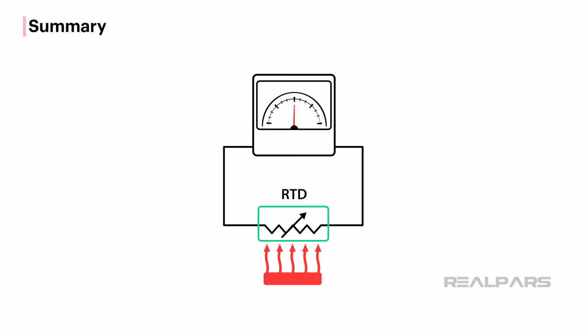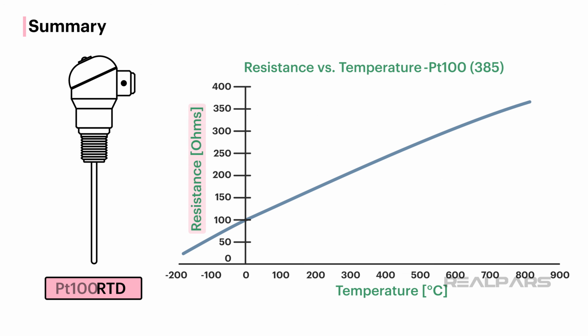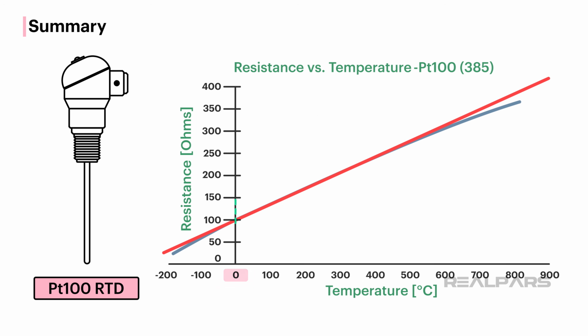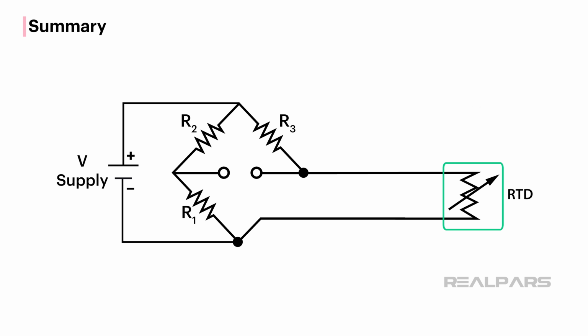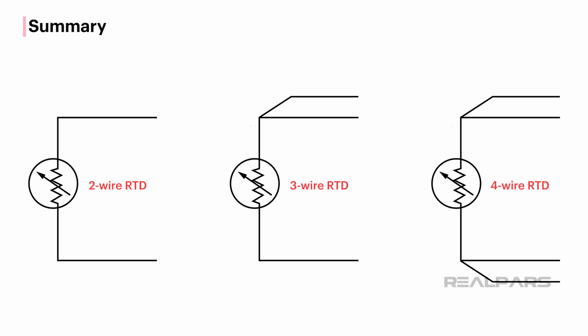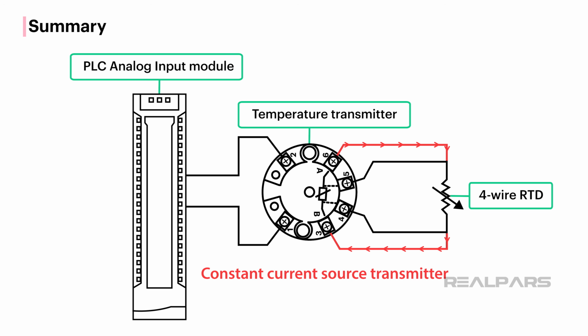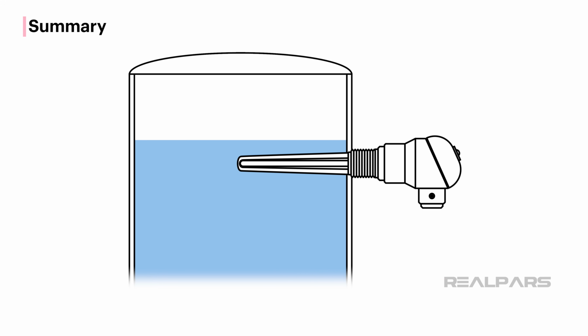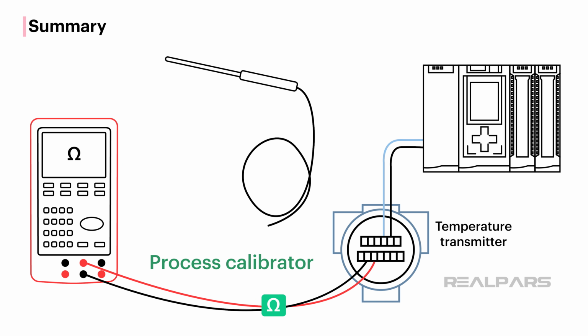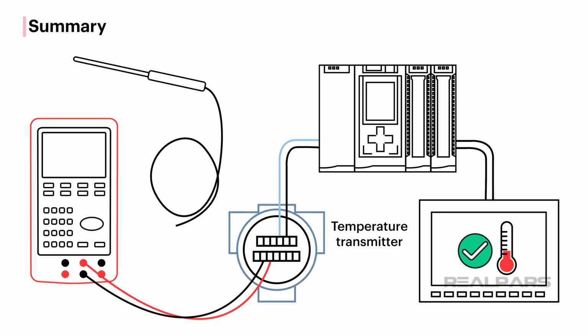Okay, let's review what we've covered in this video. An RTD is a passive resistive device made from a metal that changes resistance with a temperature change. The RTD resistance changes almost linearly with a temperature change. The Wheatstone bridge was the earliest detection circuit used with RTDs. RTDs are available in 2, 3, and 4-wire configurations. A constant current source transmitter connected to a 4-wire RTD is very common in industry. An RTD is inserted into a thermowell that is permanently housed in a pipe or a vessel. The best way to check a temperature circuit is by using a process calibrator to replace the RTD.